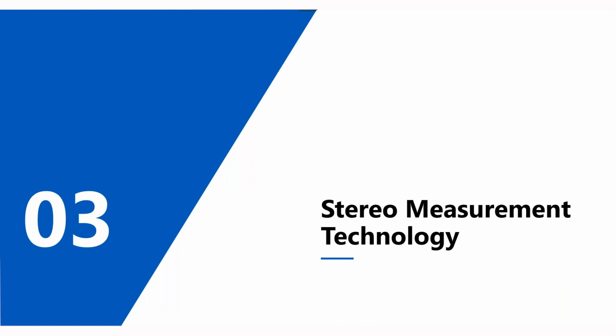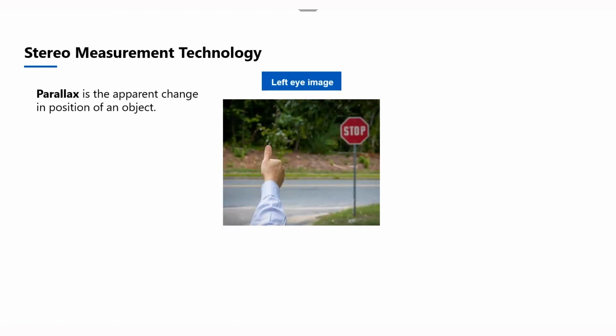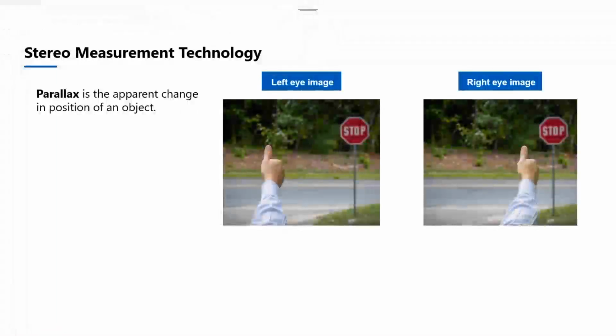Now we jump into the stereo measurement methods technology, right? This is the technology that we have implemented in Evident video scopes for performing measurements. And this technique relies on the idea of parallax.